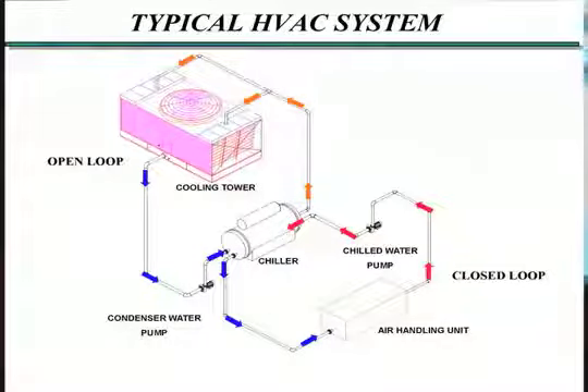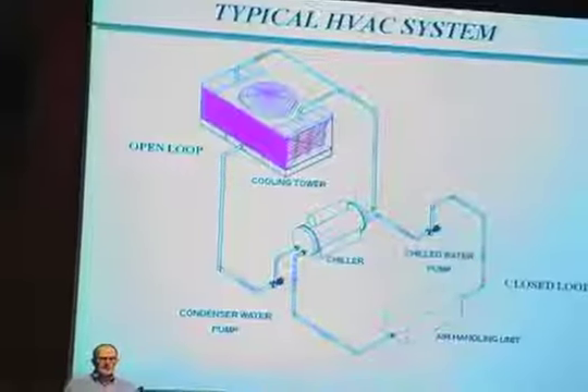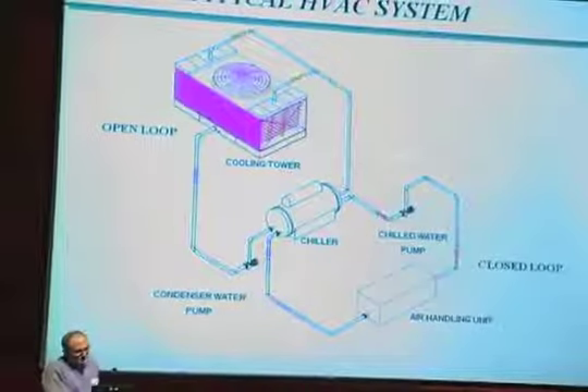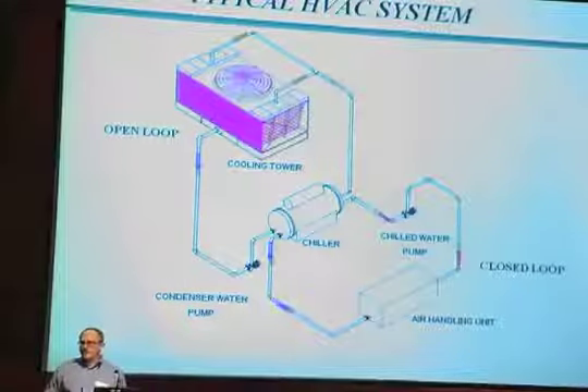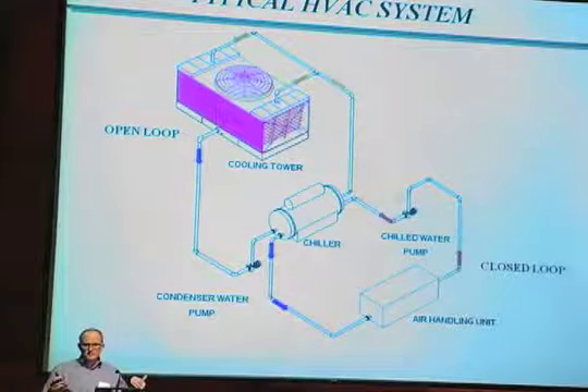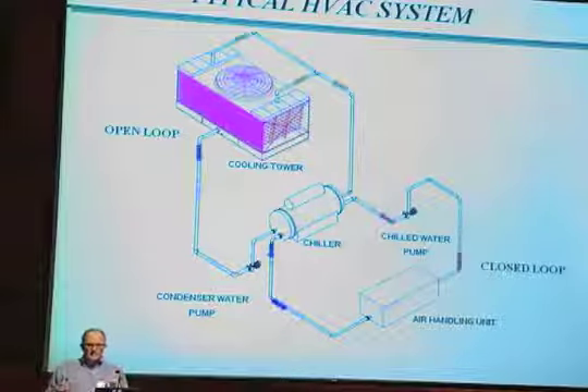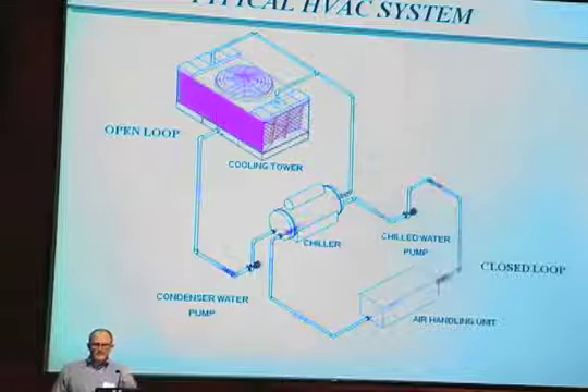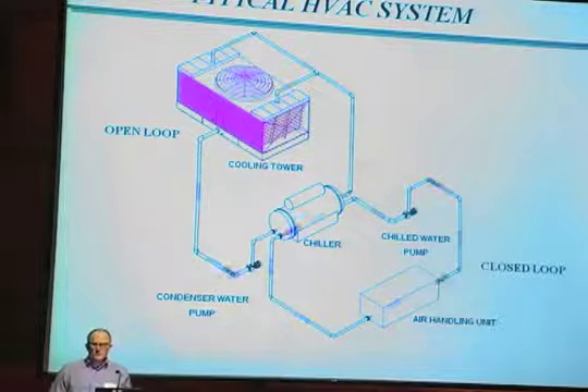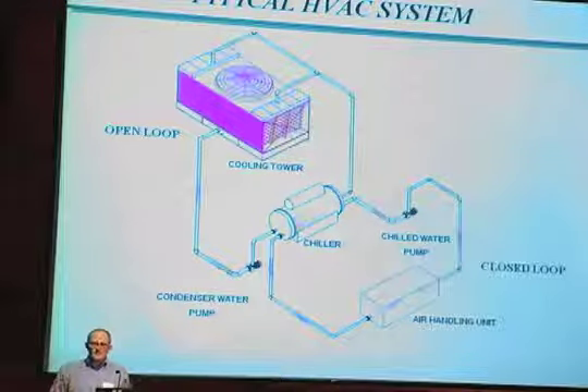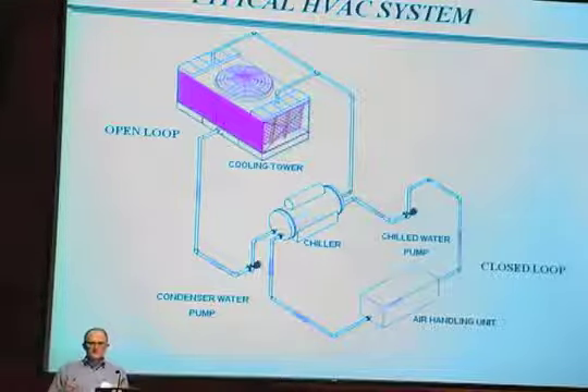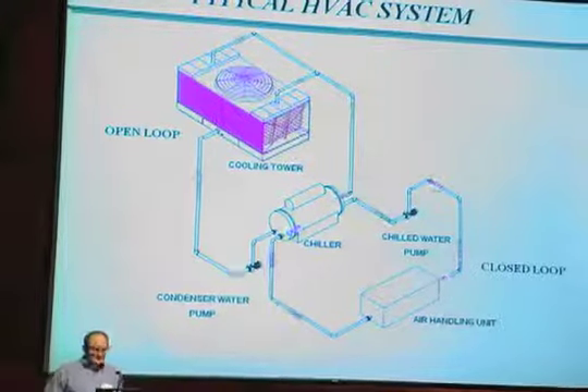What I'm going to be talking about here, and I think it's probably worth discussing this, is mostly the outside or the open portion of the cooling tower, the cooling system. That's the portion that is directly in contact with the outside air and collects this dust and dirt and debris. The closed loops portion, or typically the chilled water portion of the chillers, usually is not exposed to the contaminant loads that the outside is. There are obviously certain cases where filtration of the closed loop portion is called for. Maybe some people would even say it should always be done. But for the most part, it's a smaller or a less critical issue than the open tower because of the continual addition of particulates to the system.